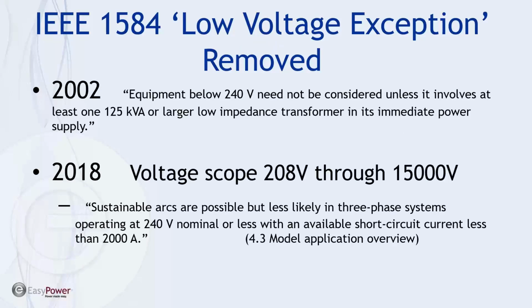Okay, for those of you that don't know, in the original version of the 1584 standard in 2002, there was a paragraph, if you will, that suggested equipment below 240 volts need not be considered unless it involves at least one 125 kVA or larger transformer in its immediate power supply. And what this resulted in was a license to basically ignore low voltage panels below 240 volts. And it allowed us to minimize the data collection at the very least.